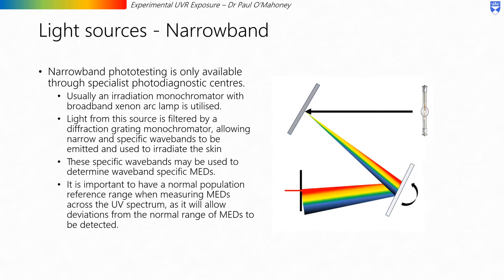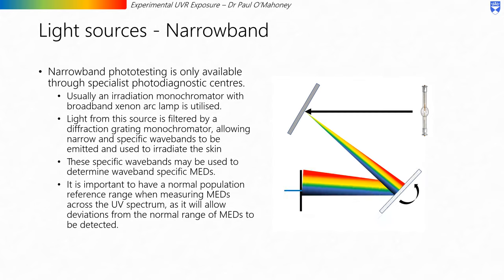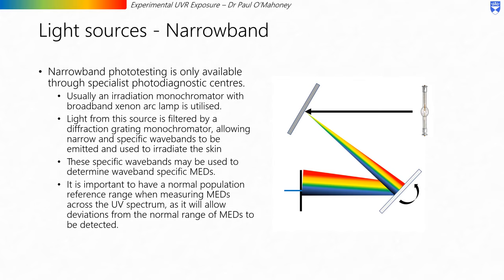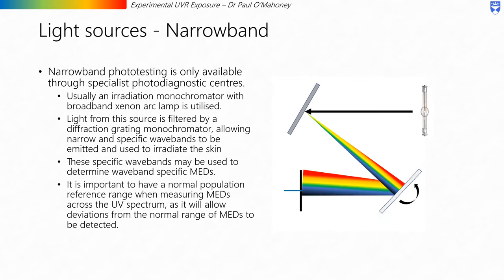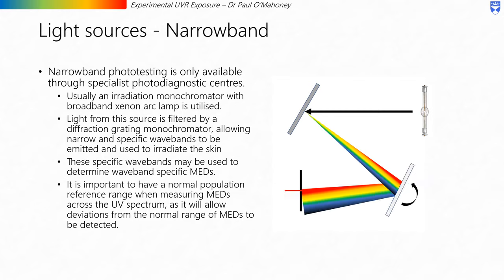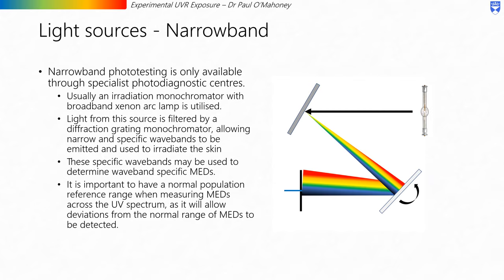When considering light sources, one type is a narrowband light source. Narrowband phototesting is typically only available through specialist photodiagnostic centres and is usually carried out using an irradiation monochromator. Light from a broadband xenon arc lamp is filtered by a diffraction grating monochromator, allowing narrow and specific wavebands to be emitted and used to irradiate the skin. These specific wavebands may then be used to determine waveband-specific MEDs. It is important to have a normal population reference range when measuring MEDs across the UV spectrum, as it allows deviations from the normal range to be detected.